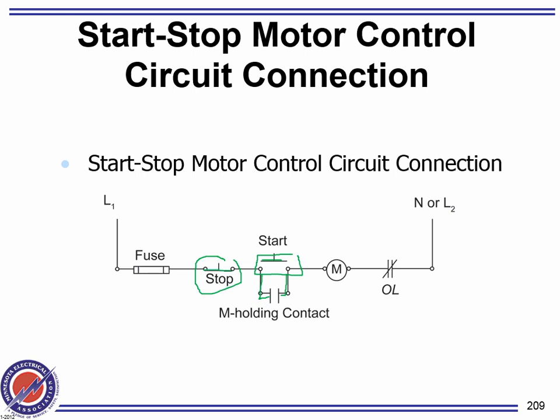The overload must always be on the side where the neutral is, if there's a neutral. If there's a neutral, you have to put the overload on the side where the neutral is. Anybody know why we do that? Because if you put it on the other side and you have a ground fault, you start your motor even when the overload is open.